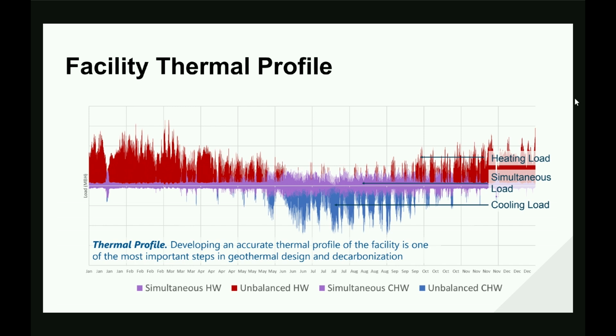Where I see heat pumps being misapplied is that people don't understand the true load profiles, or they oversize heat pumps, causing too much short cycling, which is very hard on the machine, especially centrifugals. We really need to understand the min-maxes, and that's why a phasing approach really helps in the long run, because you can actually understand what your true thermal profile is for that campus, so you don't over-design.